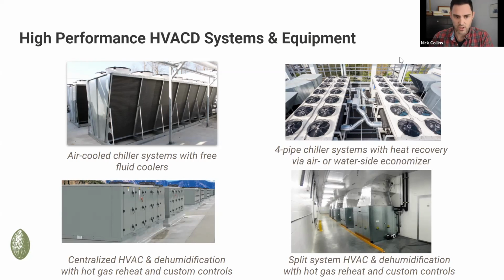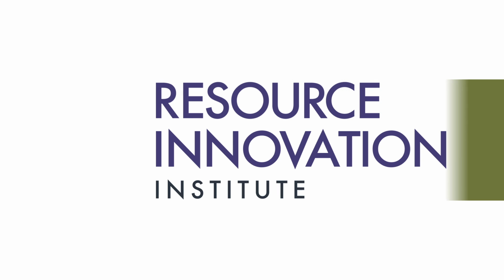With an air-cooled chiller, you can essentially shut off the compressors of the chiller system and send that cooling fluid, your chilled water with probably some glycol mixed in, out to basically big radiators outdoors with fans. And when the weather is cold outside, you can cool your facility and get the cooling loads that you need without running the compressors, which are the big energy hogs of the system. On the 4-pipe side, it's similar, though you can economize either through these dry coolers, if it's an air-cooled chiller, or right through a cooling tower with water side economizing. So those two systems give you a lot of opportunity to fine-tune the conditions of the air being delivered to the space, and for free cooling in those cold weather climates. And that can take a lot of the energy typically associated with cooling right off.